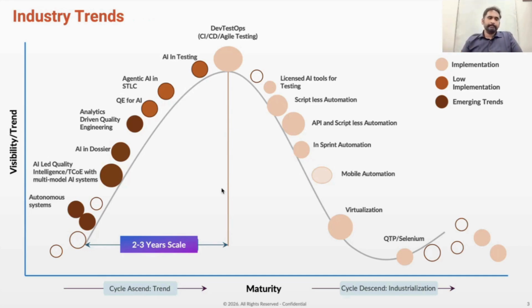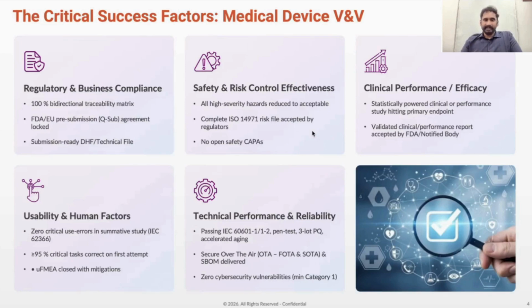So what could be those critical success factors for a medical device? We must have regulatory and business compliance for sure, ensuring the safety and risk control effectiveness, bringing in the clinical performance and efficacy, considering all the usability and human factors, and technical performance and reliability, of course. While we are ensuring all these things, we need to continuously take care of traditional validation and verification initiatives, be it at the functional side or the non-functional aspects, adhering to all the IEC and ISO standards and guidelines, adhering to the FDA and EU pre-submission guidelines. All these things play a major role in the success of a medical device.